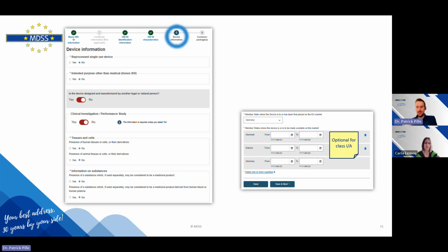The disadvantage of selecting more countries than where you know the device is actually supplied is in case there's a reportable incident. God forbid, we don't hope for that, but in case a device causes an incident in France, all authorities of the member states have access to the vigilance data. And if the authority in Sweden, for example, sees that the device is indicated to be available in Sweden, whereas it is not, but it's indicated in EUDAMED, then the Swedish authority may reach out with questions about whether and how many devices have been shipped to Sweden, if any, so any potential surveillance actions that could then be asked by the authority.